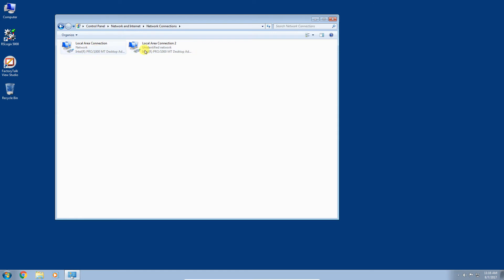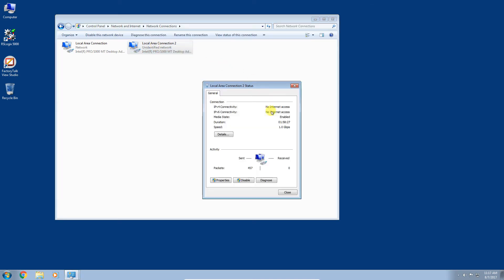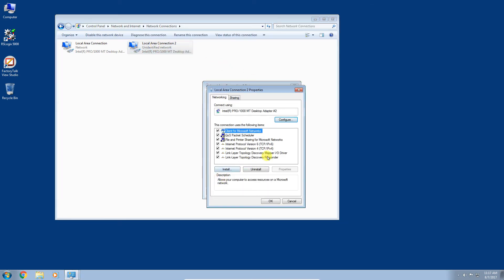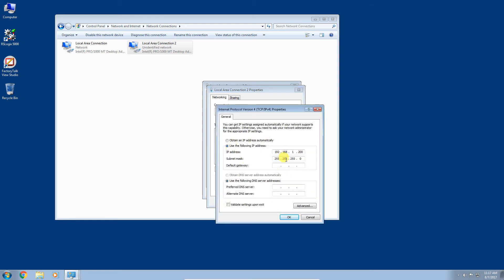You can see here I have two network interface cards in this computer — or this VM. Local Area Connection 2 is the interface connected to the network that my controller is on. We want to double-click it, go to Properties, select Internet Protocol Version 4, and click Properties again. I already have a static IP address configured on the same network as my PLC. My PLC's Ethernet bridge module IP is 192.168.1.10, and I've set my computer to .200.